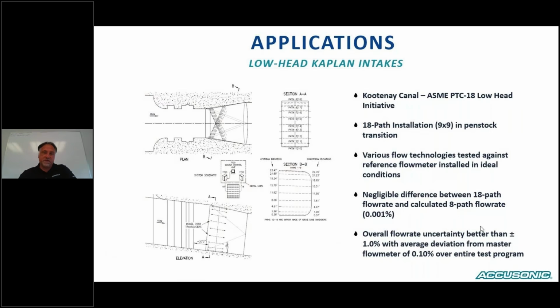But after the test, we found out that we were within 0.1% over the entire test program. And we were also able to back calculate what the difference would be between the 18-path system and the 8-path flow. And that was obviously very, very negligible, 0.001%. So typically in this type of low head Kaplan intakes, we can get better than a percent.